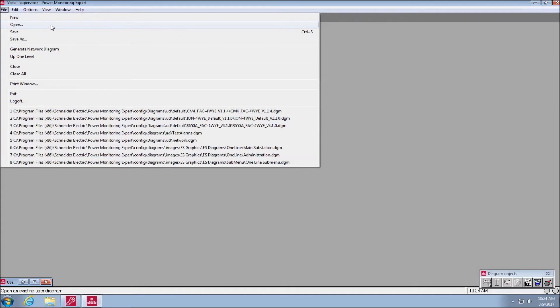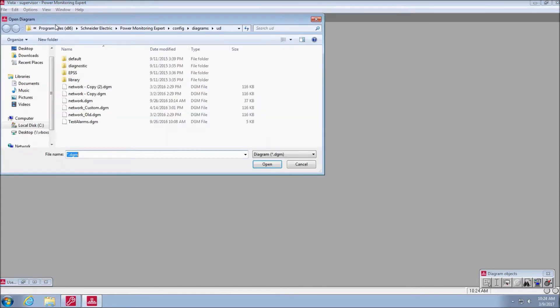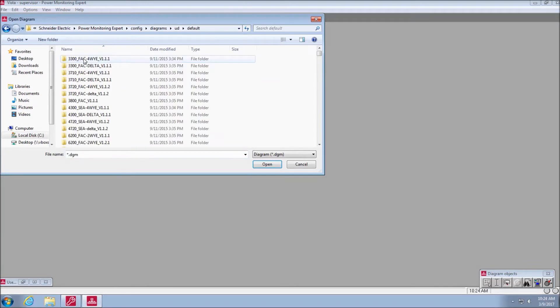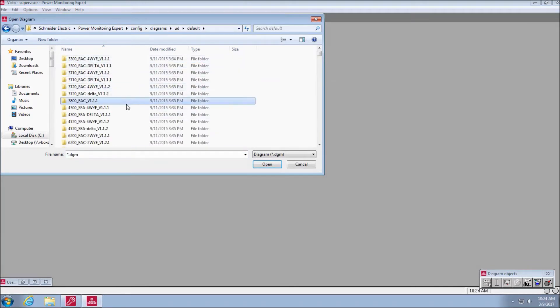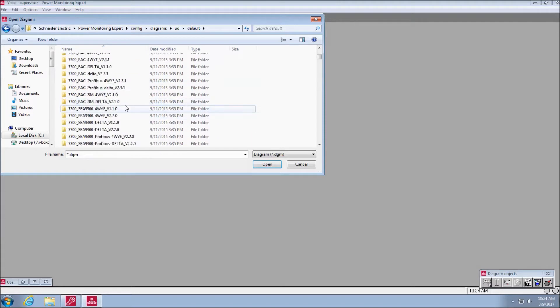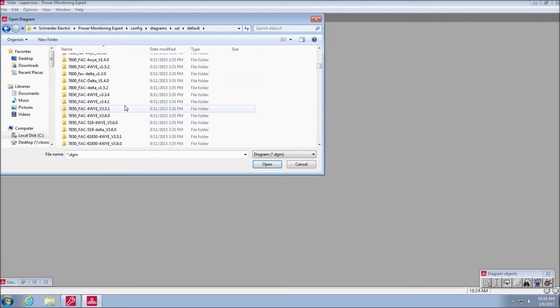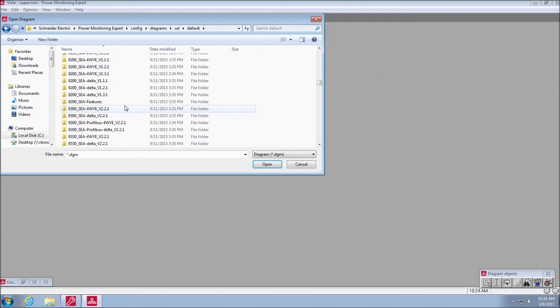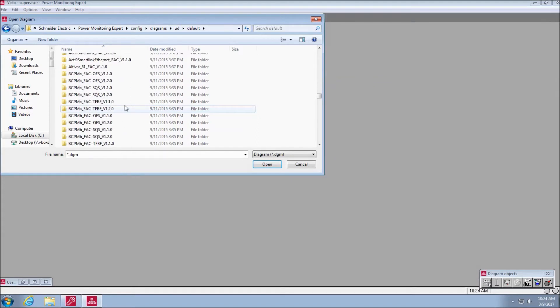A common problem when working inside Vista is for template diagrams to be saved to a specific meter. This creates a situation where all devices of that same type will open an incorrectly saved diagram. Each folder shown here contains a pre-configured set of diagrams for a specific device type and firmware revision.